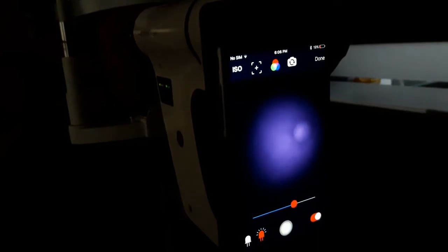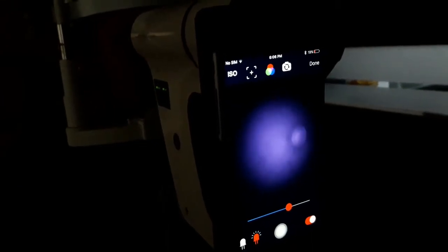Ensure that the pupil is located at the center of the live view. In the infrared mode, move into the pupil. Ensure that the pupil is at the center. At the appropriate working distance, by moving the joystick left or right or up and down, you will now see a very clear infrared view of the retina.